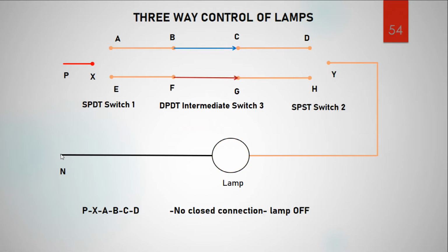Now consider the DP/DT intermediate switch in straight connection. Observing the SP/DT switches, one is connected to A and one to Y. Tracing the path, it is cut here with no further movement, and cut again here, so there is no closed path for current to flow. With no phase-neutral connection, the lamp will not glow.